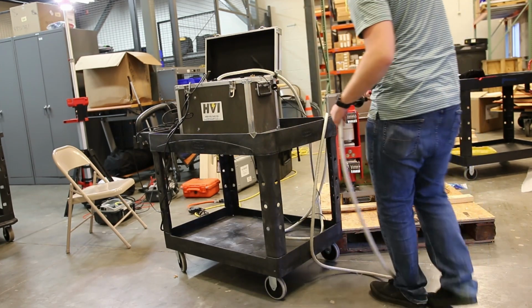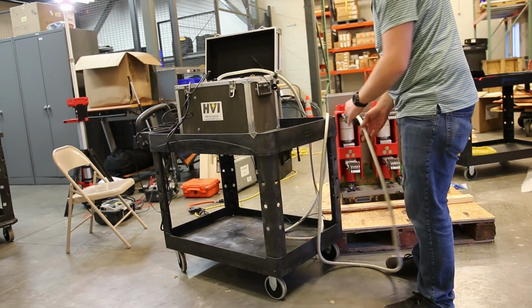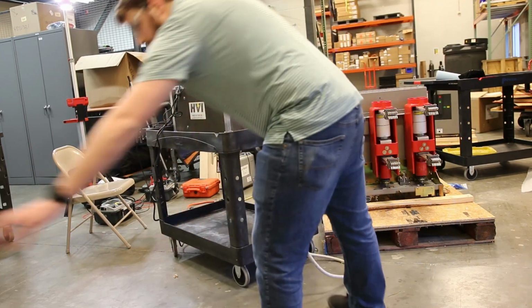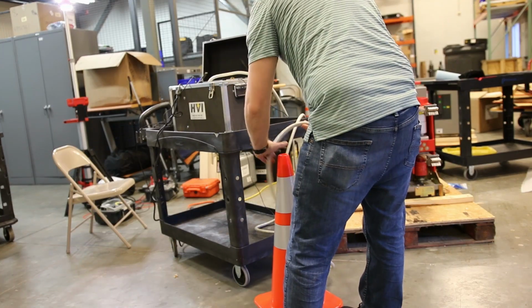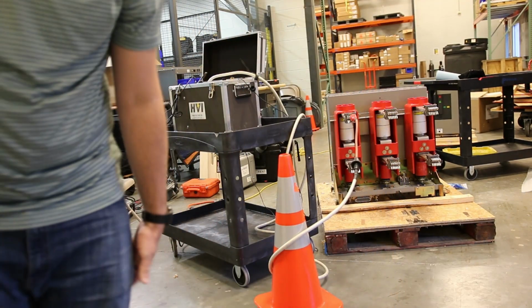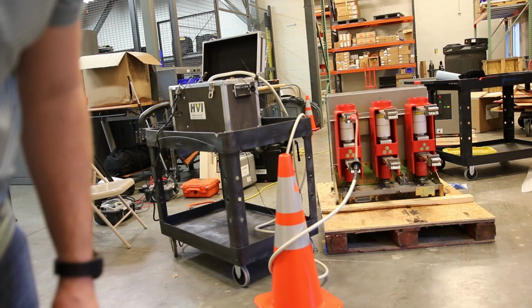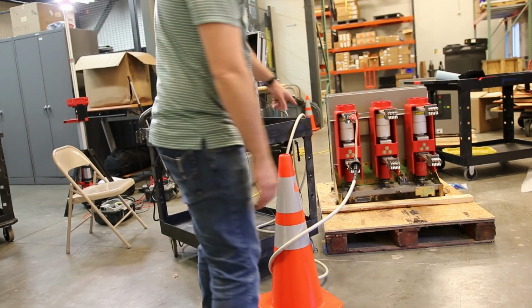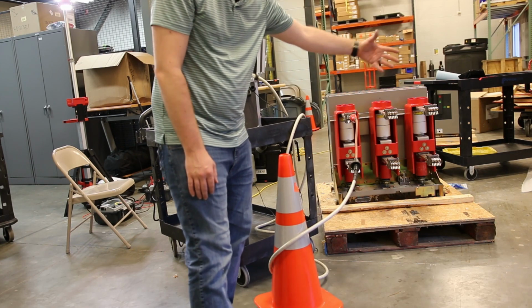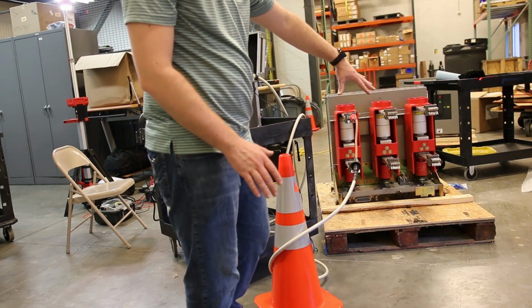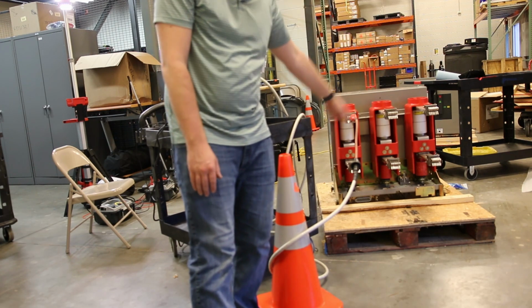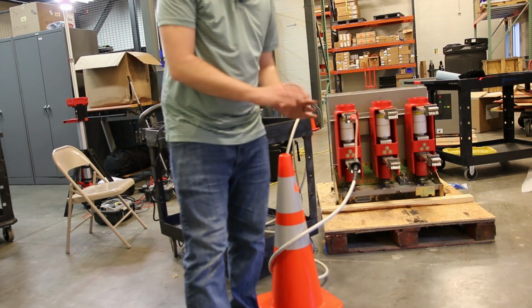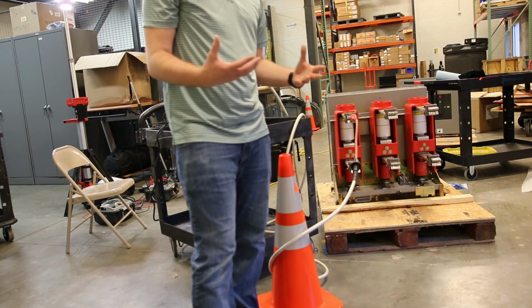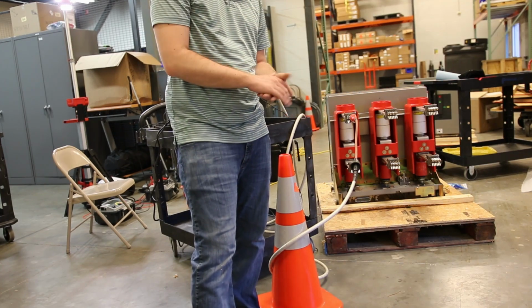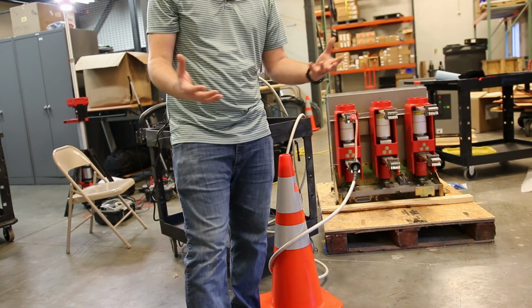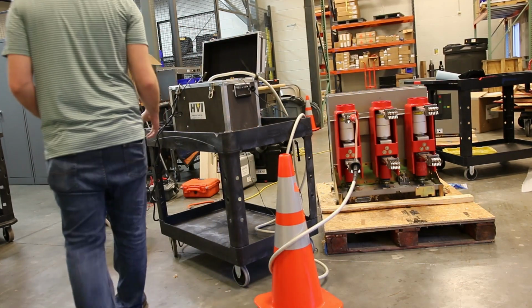And so we wanna hang this away from everything else that we're testing. And we've got a couple different ways we can do that. I like to hook it around something, just get it out of the way. Make sure that big bright orange cone is right in the middle of the shot. That's perfect. And then like I said, the bottom of that pole and then the other two poles are all gonna be grounded. So everything on this, the top of B and C, and the bottom of A, B, and C are all gonna be grounded. And then when we high pot, we're checking essentially all of the current leaving the test set going to ground. That's my return value.